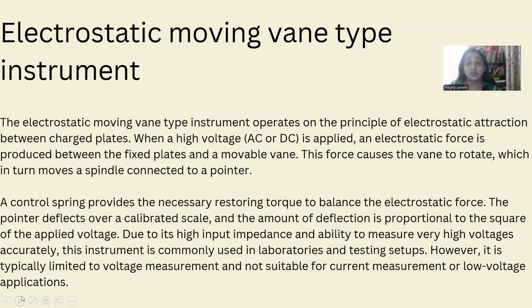This force causes the vane to rotate, which turns a spindle connected to a pointer. A control spring provides the necessary restoring torque to balance the electrostatic force. The pointer deflects over a calibrated scale, and the amount of deflection is proportional to the square of the applied voltage. So it is used for measurement of AC voltage. Due to its high input impedance and ability to measure very high voltage accurately, this instrument is commonly used in laboratories and testing setups. However, it is typically limited to voltage measurement and not suitable for current measurement or low voltage applications.